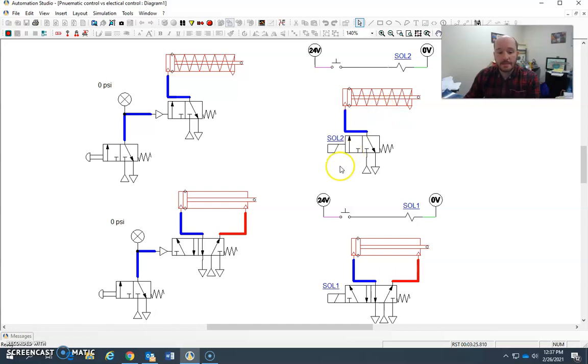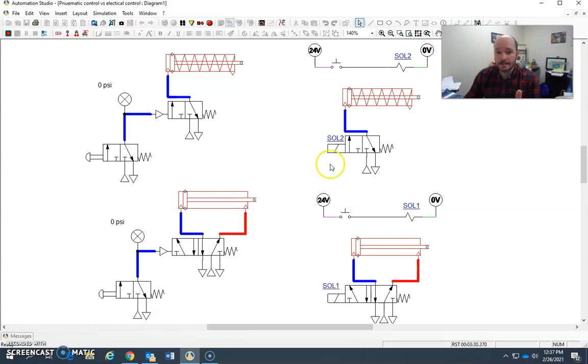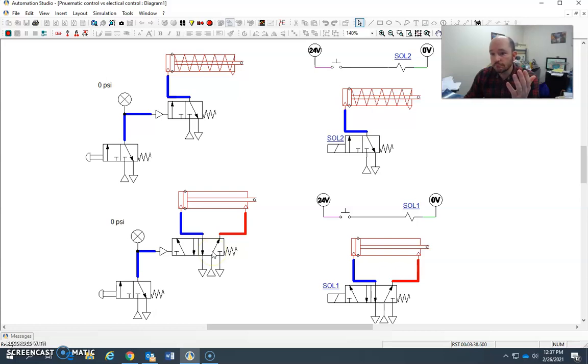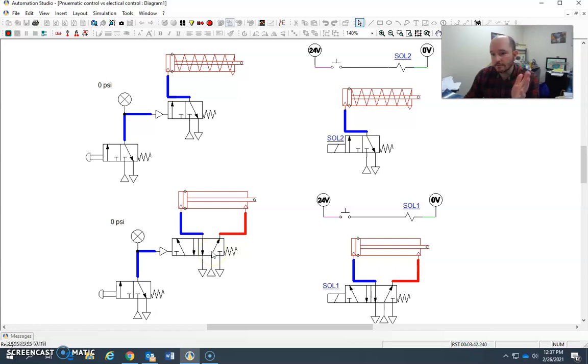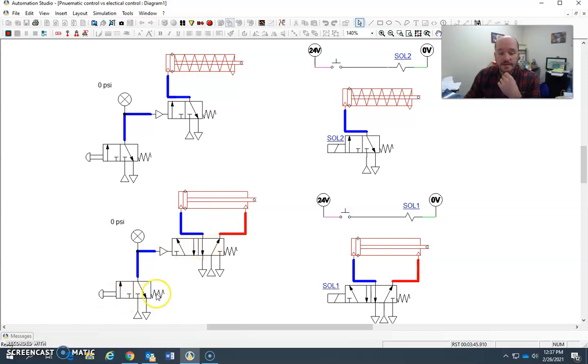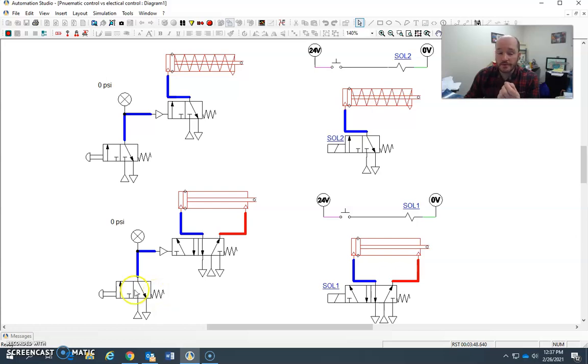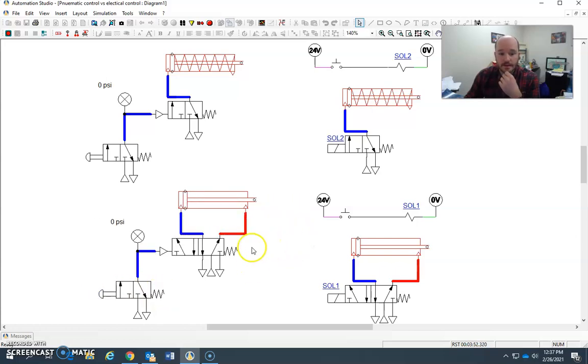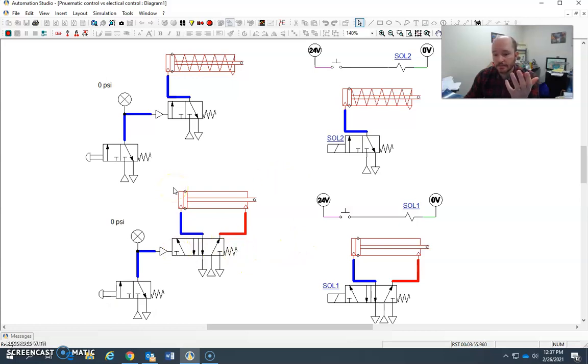We can expand the conversation on this to just get to a double-acting cylinder that's going to operate and behave exactly the same. Here I have a 5-2 directional control valve being controlled by a 3-2. Again, this can be located within a couple of feet, maybe up to 10 feet or a little bit farther if it had to be, from the cylinder. This can be located at the operator station or wherever is needed. So I activate this, extend the cylinder, I let it go, the spring return here pushes it back, the cylinder retracts.